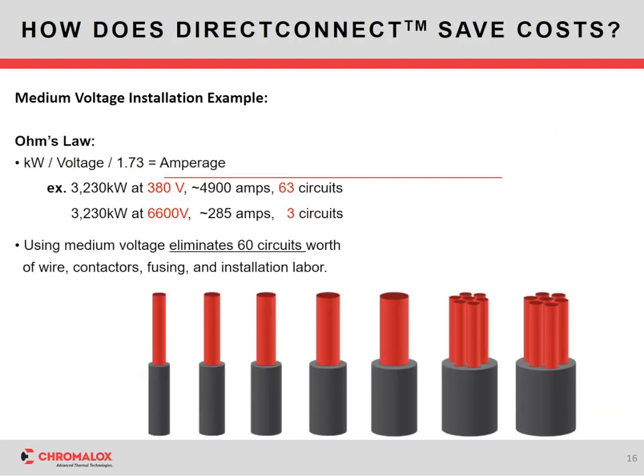So when we put this into practical terms, again from our case study, first what we're going to look at is a system that needed a little over 3,000 kilowatts worth of power. Now in a traditional system at 380 volts, that would be 4,900 amps. And so from an installation standpoint, somebody would have to put in 63 circuits worth of wiring out there.